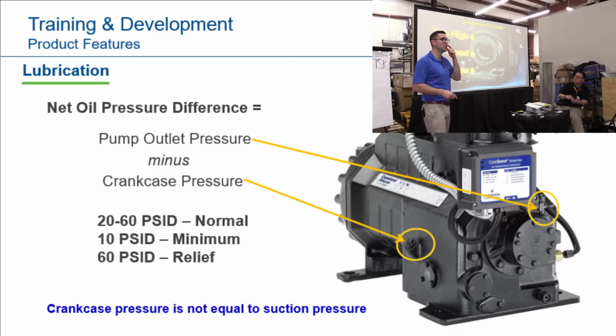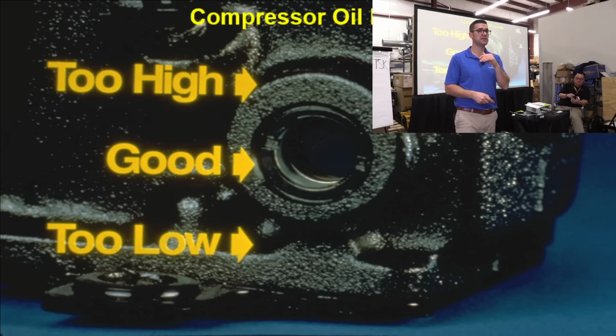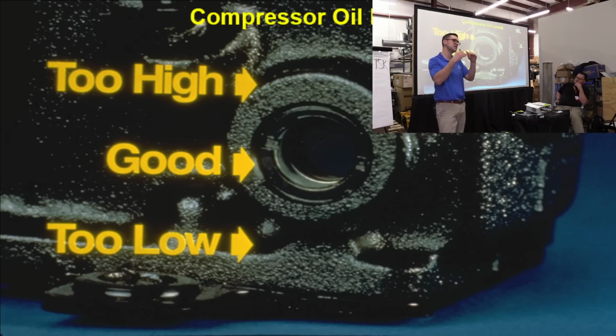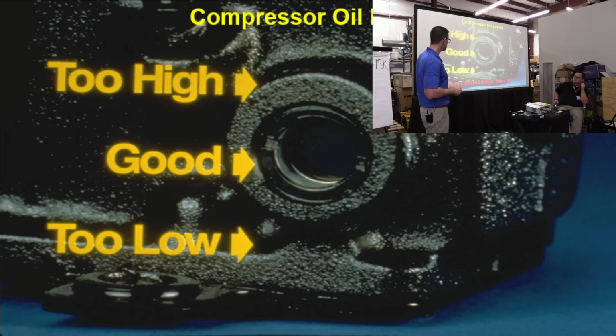So where's a good oil level in a compressor? Half sight glass. There's some models where we say a quarter or some three-quarters. Half sight glass. If you're looking at a half sight glass, that's what you're looking for. More oil is not always better, because that could be liquid refrigerant pushing up that oil too.